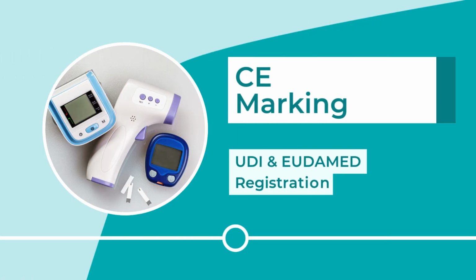With the certificate in hand, the manufacturer affixes the CE mark, assigns unique device identifiers, and uploads device data to EUDAMED. Labels, instructions, and marketing claims must precisely match the evidence contained in the technical file, nothing more, nothing less.